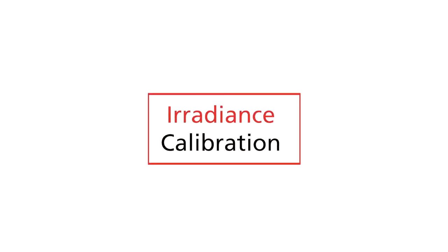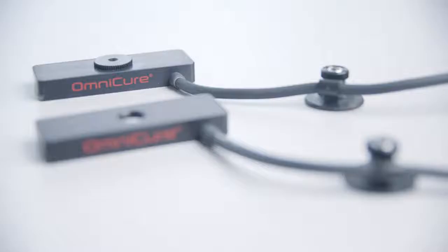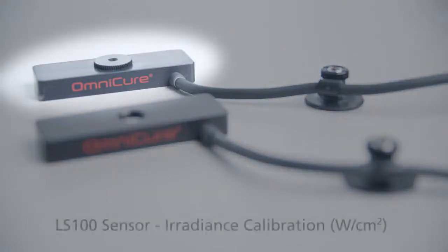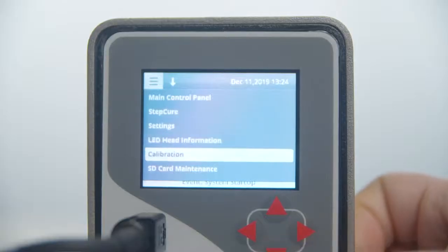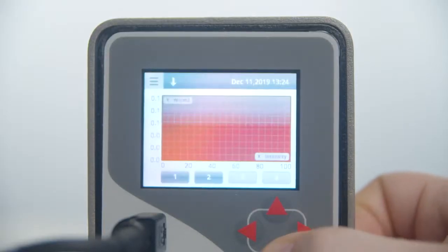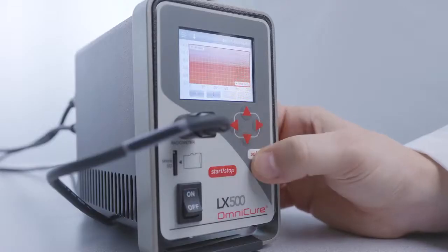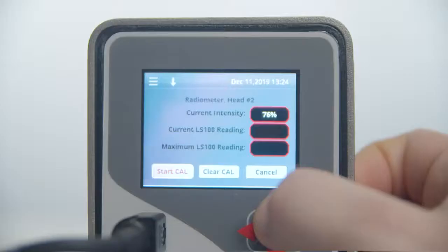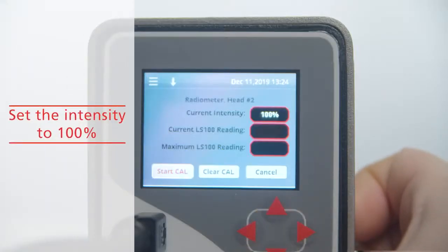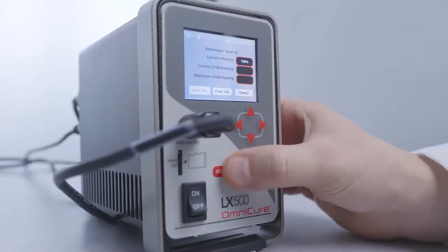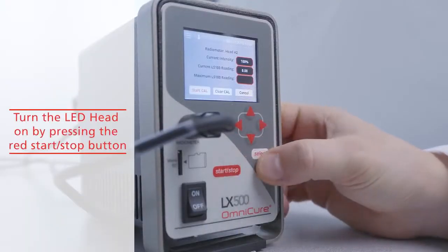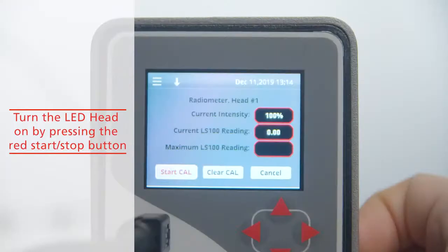Next, we'll do an irradiance calibration. Once the irradiance calibration kit using an LS100 sensor has been assembled and connected to the LX500 controller along with the LED head, the LX500 controller can be turned on and calibration can be initialized. Calibrating the irradiance is very similar to calibrating the power. First, set the intensity to 100% by using the arrow key. Turn the LED head on by pressing the red Start/Stop button. The head can be confirmed turned on once the values start appearing on the screen.